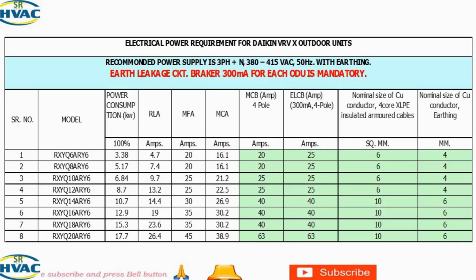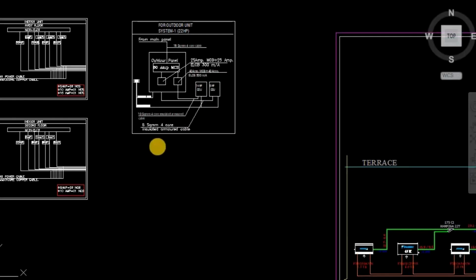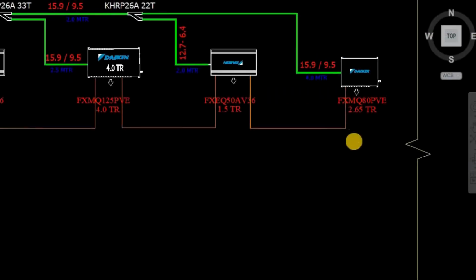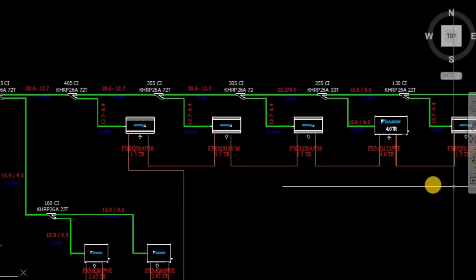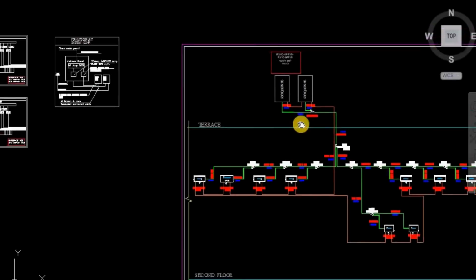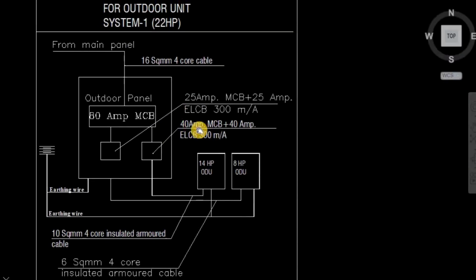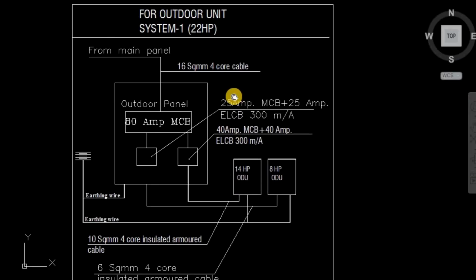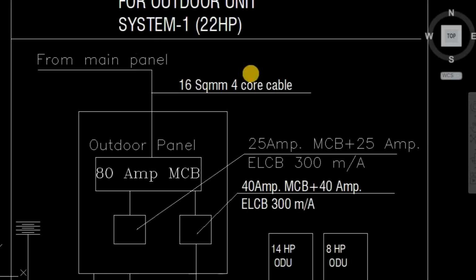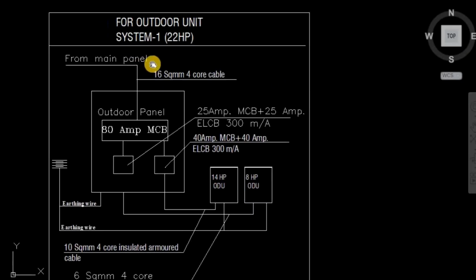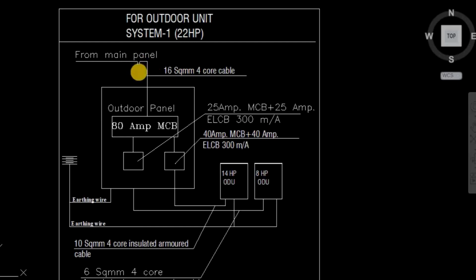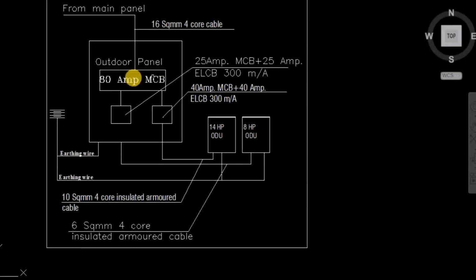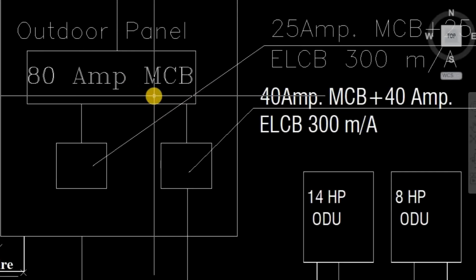Okay friends, and now we will see one project so we can understand properly. You can see this is the communication cable. We will come to the communication cable in the next part. In the second part we will see some electrical details for outdoor unit. This is a system of 22 HP. You can see the main cable is coming, 16 square mm 4 core. Then MCB will be 80 ampere.